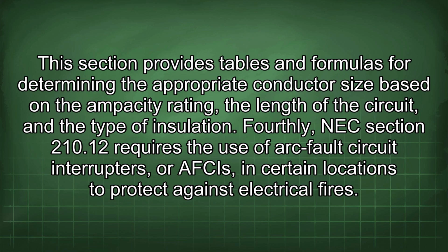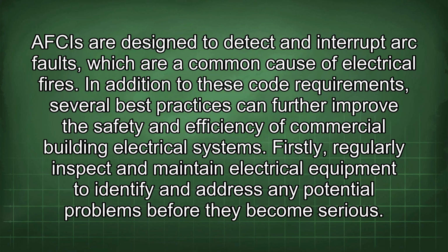Fourthly, NEC Section 210.12 requires the use of arc fault circuit interrupters, or AFCIs, in certain locations to protect against electrical fires. AFCIs are designed to detect and interrupt arc faults, which are a common cause of electrical fires.